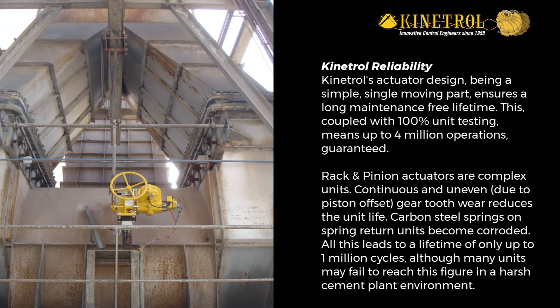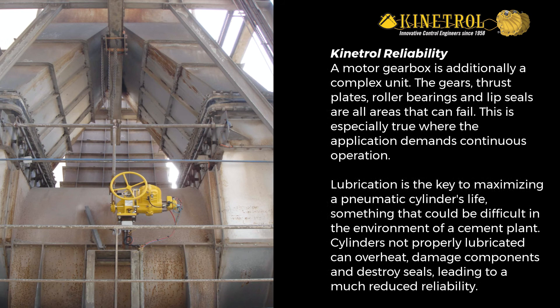Rack and pinion actuators are complex units. Continuous and uneven wear, due to piston offset and gear tooth wear, reduces the unit life. Carbon steel springs on spring return units become corroded. All this leads to a lifetime of only up to 1 million cycles, and many units may fail to reach this figure in a harsh cement plant environment. A motor gearbox is additionally a complex unit; the gears, thrust plates, roller bearings, and lip seals are all areas that can fail, especially where the application demands continuous operation.